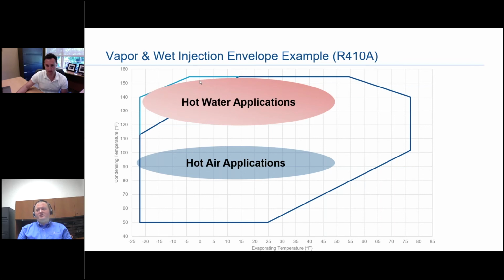And if you have vapor injection on there, that drastically helps the efficiency of that system. But if it's real cold outside, negative 10 degrees, and you're still wanting to make 150-degree hot water, you're not typically going to be able to do that with compressor technology. You may be able to get 135 or 140, but typically you're going to have limitations as you go colder on the outside air temperature, based on what the hot water condition is. The downfall is that's kind of the opposite of what you want. A lot of times if it's colder outside, you may want hotter hot water at that point. But there's limitations based on what that high compression ratio condition is and what that high discharge temperature leads to.